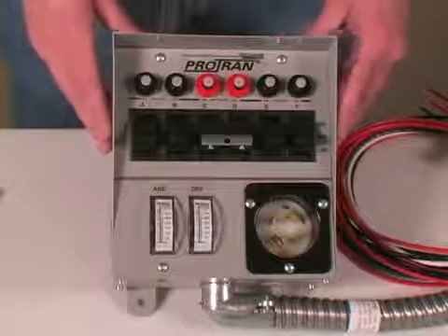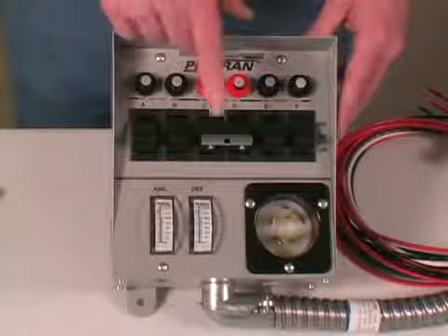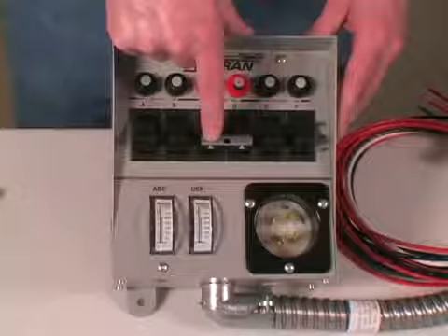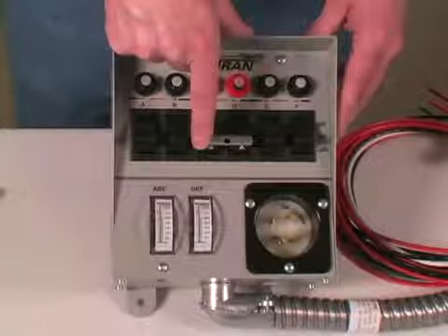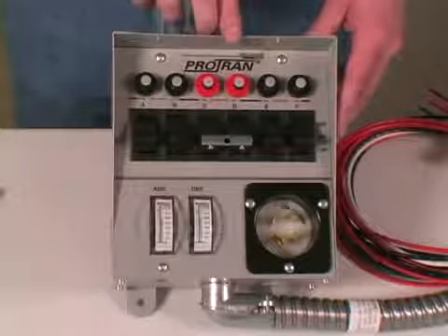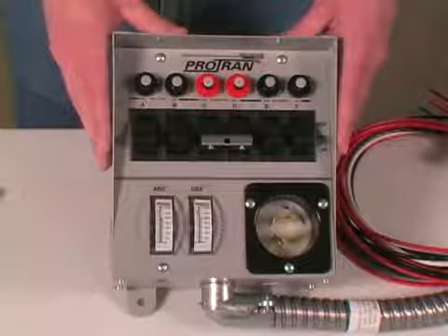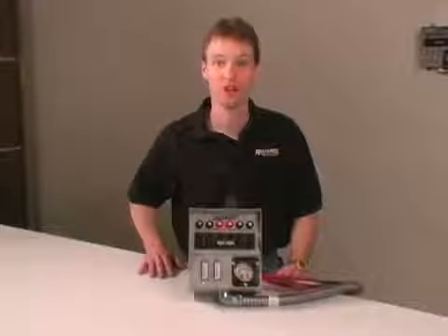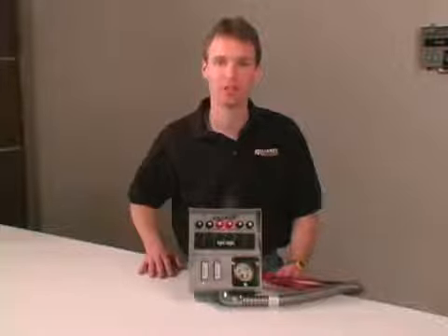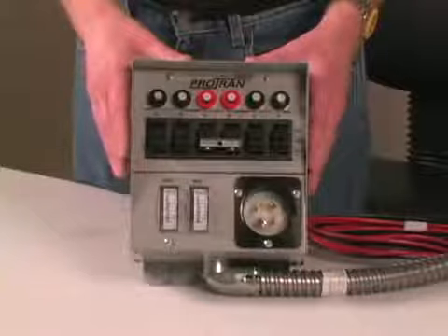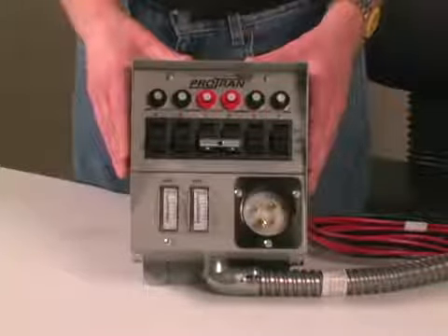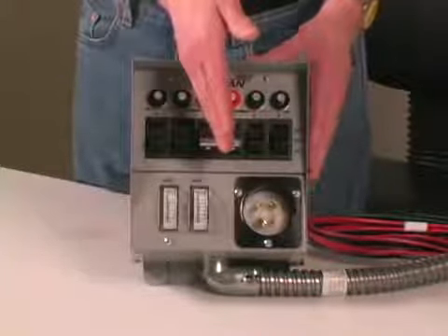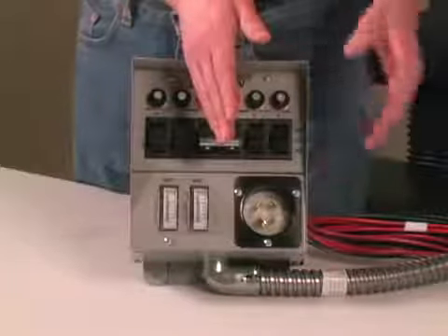If you don't need to power a 240 volt circuit, this handle tie can be removed with the 2 screws, and the C and D switches can operate 2 separate single pole or 120 volt circuits. Your generator will operate most efficiently if you can divide the power used evenly between the 2 sides of the transfer switch. Think of your generator as having 2 outputs, one that powers one half of the transfer switch and one that powers the other half.